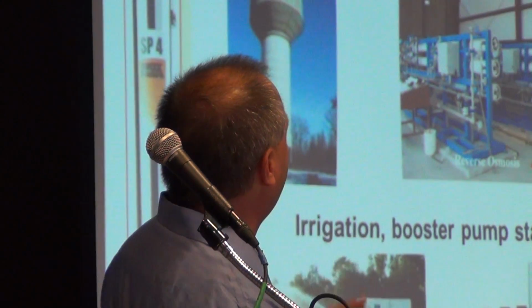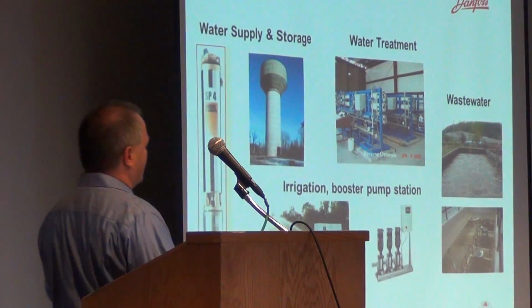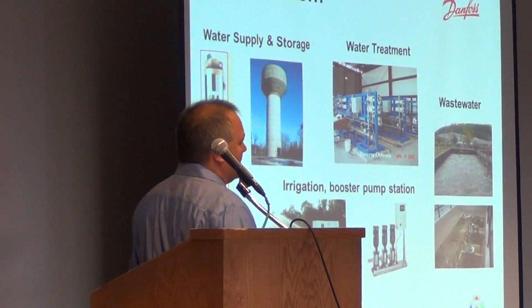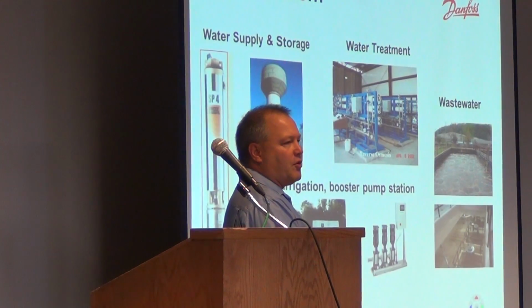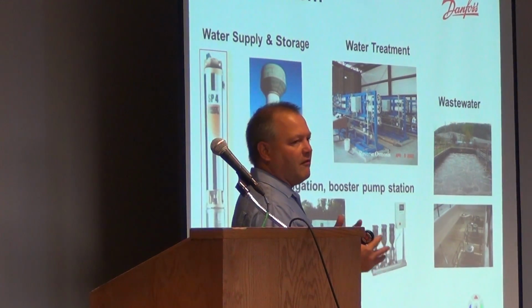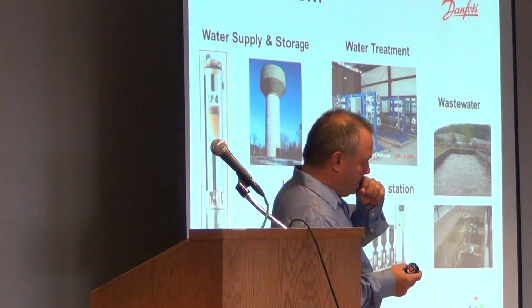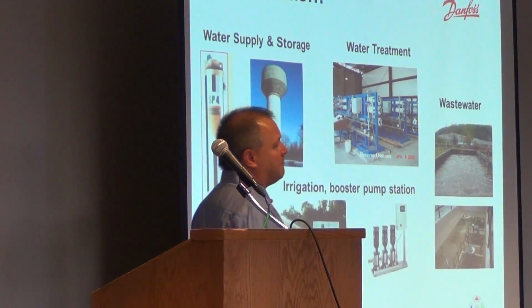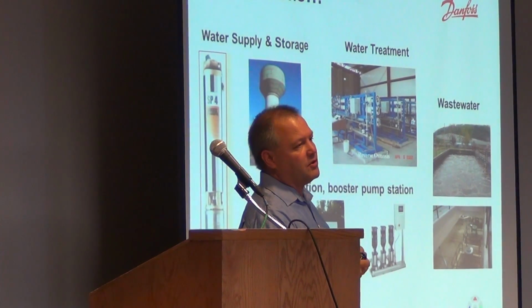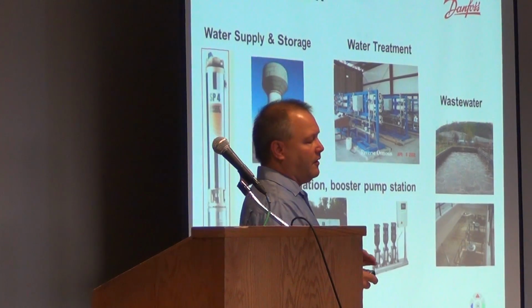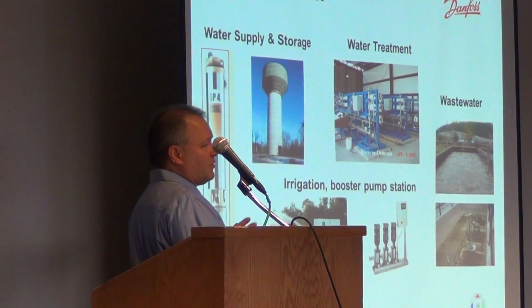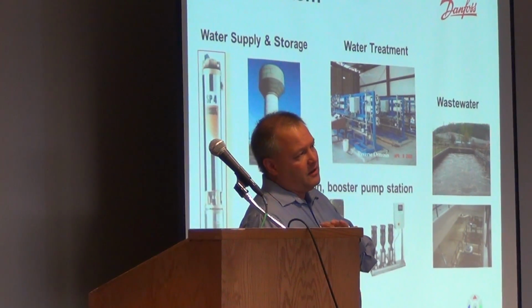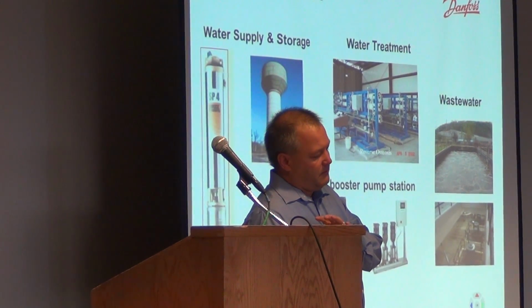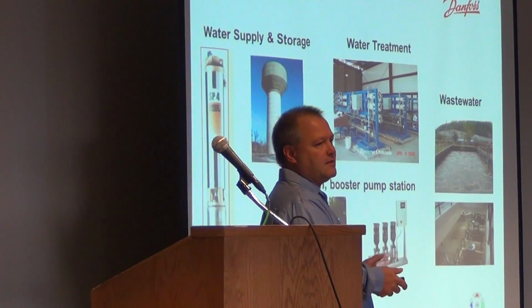So, some of the places that we can conserve energy or use drives: water supply applications, water treatment, wastewater, irrigation, booster stations. It's basically a three-phase motor and you're holding it back somehow, valving it back, or have some type of restriction in the pipe. A VFD might be able to help you conserve energy by reducing the speed of the motor. There are applications where it doesn't save you money on the energy side, but it saves you money on the maintenance side.